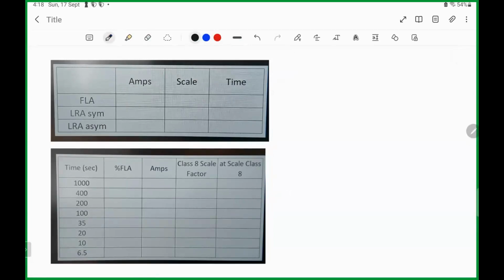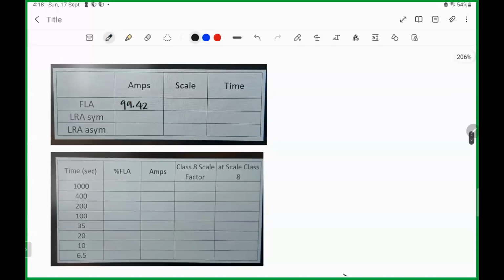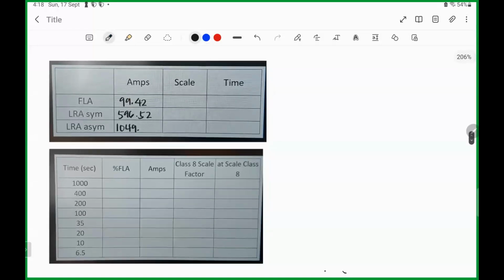So yung na-calculate natin, 99.42, which is the full load amps. Our LRA symmetrical is 596.52, and LRA asymmetrical is 1049.88. So what is the time? The FLA is continuous, so non-trip. Sabi natin yung LRA, we assume the LRA symmetrical is at 5 seconds, and the LRA asymmetrical, definitely this is 0.1 second. So mamaya, plot natin yan.